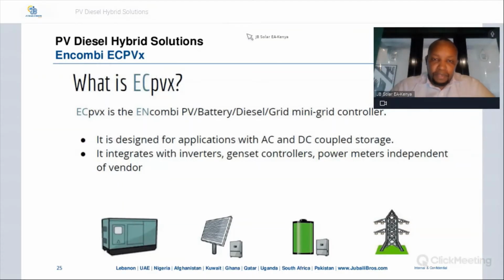So what is the ECPVX? This is the controller that controls the PV, battery, diesel, and the grid. So it integrates all these different sources of energy and makes them work hand in hand. It has been designed to work with both AC and DC coupled systems, and it integrates with different power components regardless of vendors, be it the diesel generator, the PV array system, the battery energy system, as well as the grid. So the ECPVX will work with whatever brand of diesel generator or PV system that you're working with.